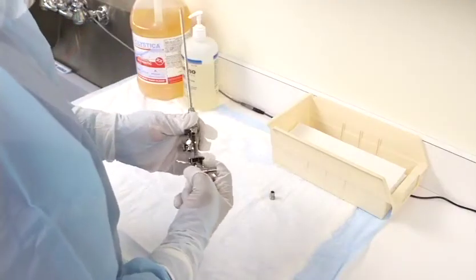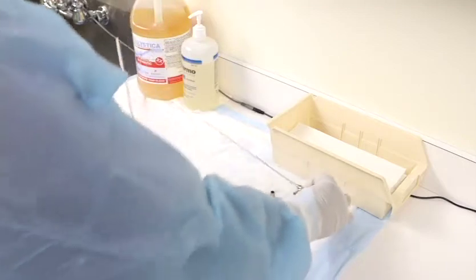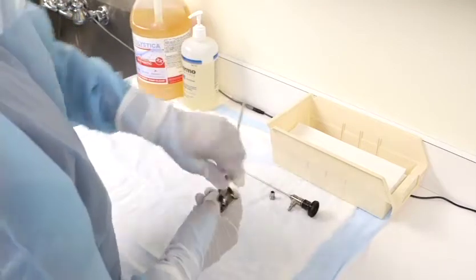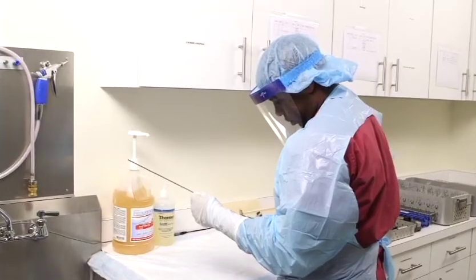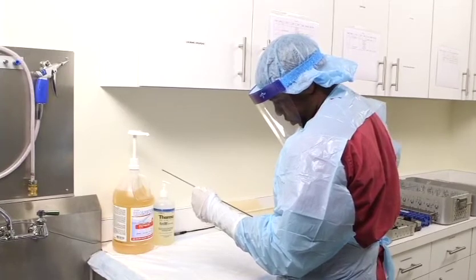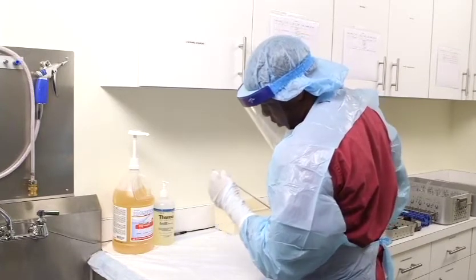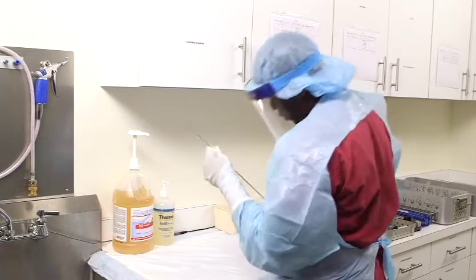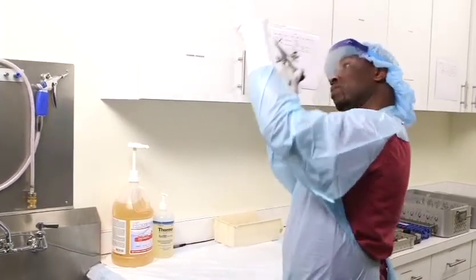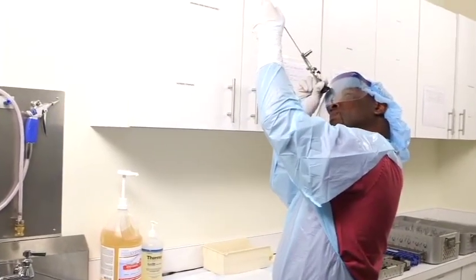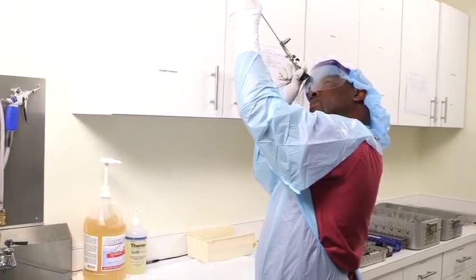Remove the endoscope from the scope protector or any assemblies and sheaths not yet disassembled in the patient care area. Inspect the shaft of the endoscope to detect any dents or scratches. Inspect the optical lens and eyepiece lens for any cracks or fogging. Check the epoxy by the optical and eyepiece lens to ensure it is intact around each lens.